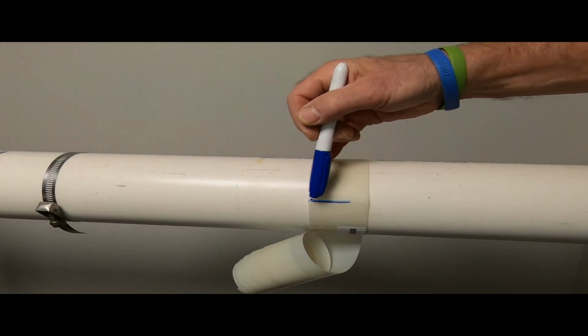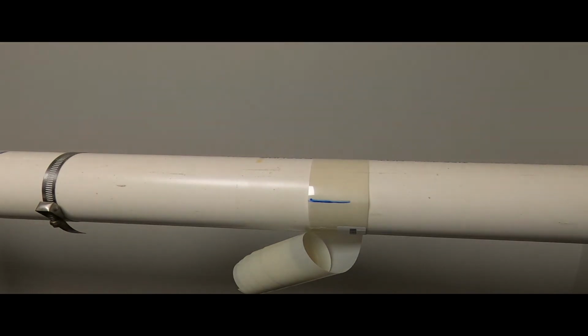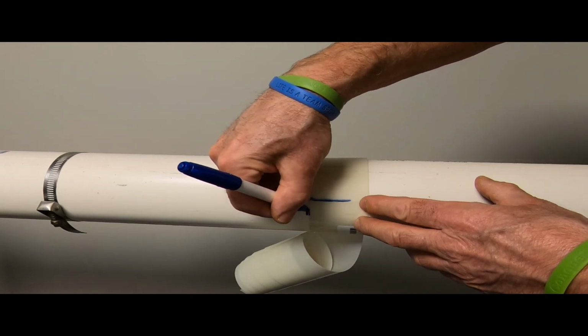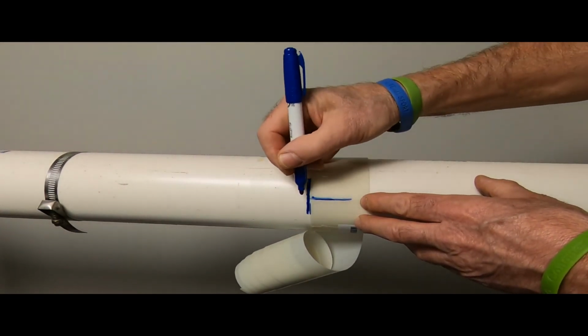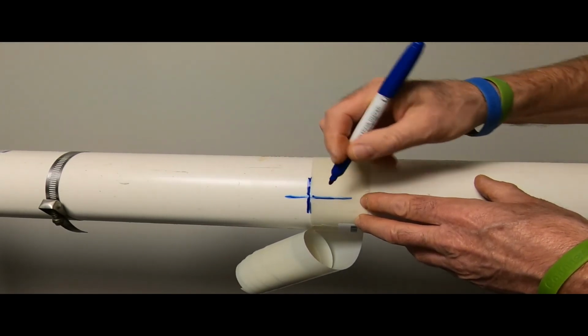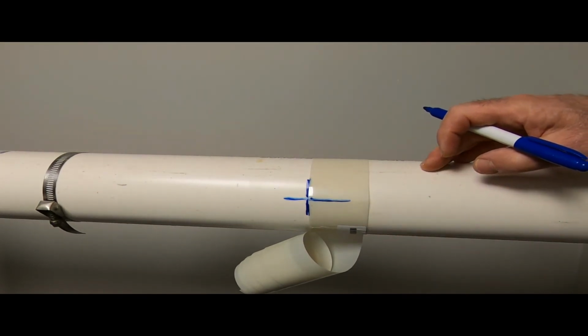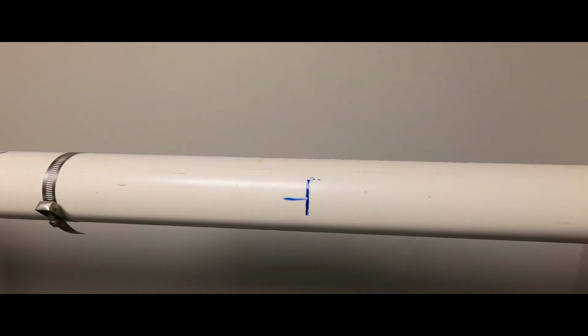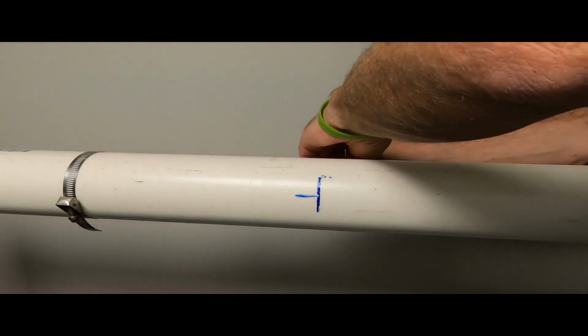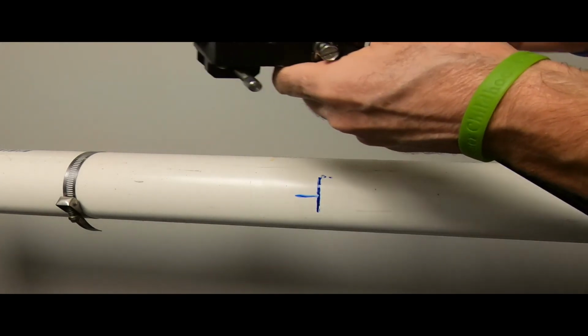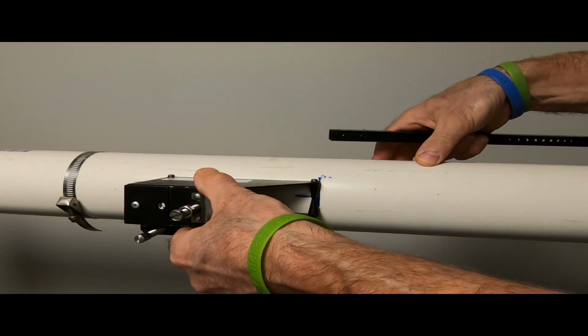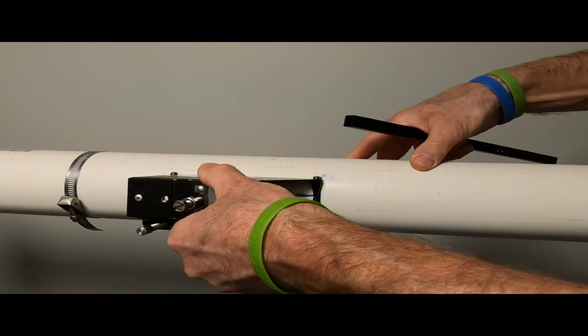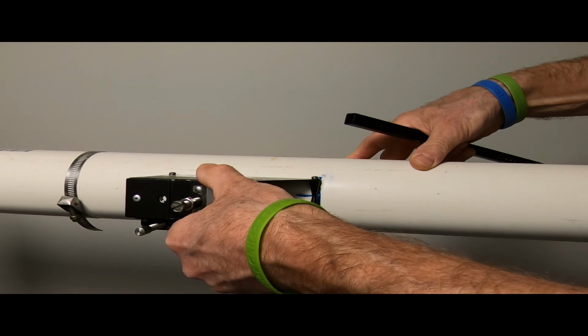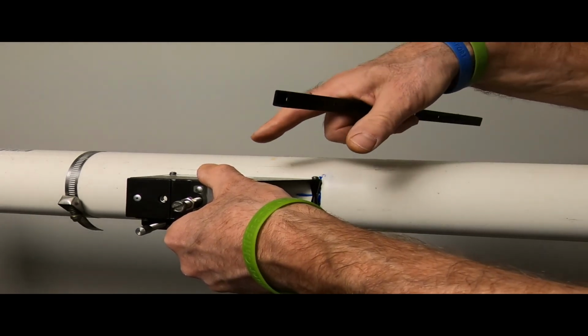Now that we're on the opposite side of the pipe, we can see the line that we made at the fold that we created in the mounting guide. What you can now do is make a line along the edge of the mounting guide that you will line up your mounting frame with, and also another line that's directly in line with the mark that we made on the mounting guide fold, which will be the center point of your mounting frame. Once you've done this, you can remove the mounting guide from the pipe. Next, remove the spacer bar from the mounting frames and swing the unstrapped mounting frame around to the opposite side of the pipe, centering it on the line that you created along the pipe's axis and lining it up with the perpendicular mark you made on the pipe. This establishes the correct spacing and ensures that the two mounting frames are 180 degrees apart. Now all you need to do is strap the frame to the pipe.